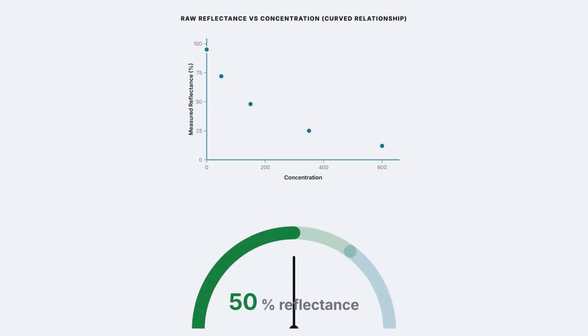In practice, this is exactly why dry slide calibration curves are rarely simple straight lines. Instrument software applies the Kubelka-Munk transformation, or an empirically derived equivalent, to convert raw reflectance into a linearized concentration value, which is also exactly why forcing dry slide data into a simple linear calibration model, as covered in the broader calibration discussion, would be a genuine chemistry-level mistake here.